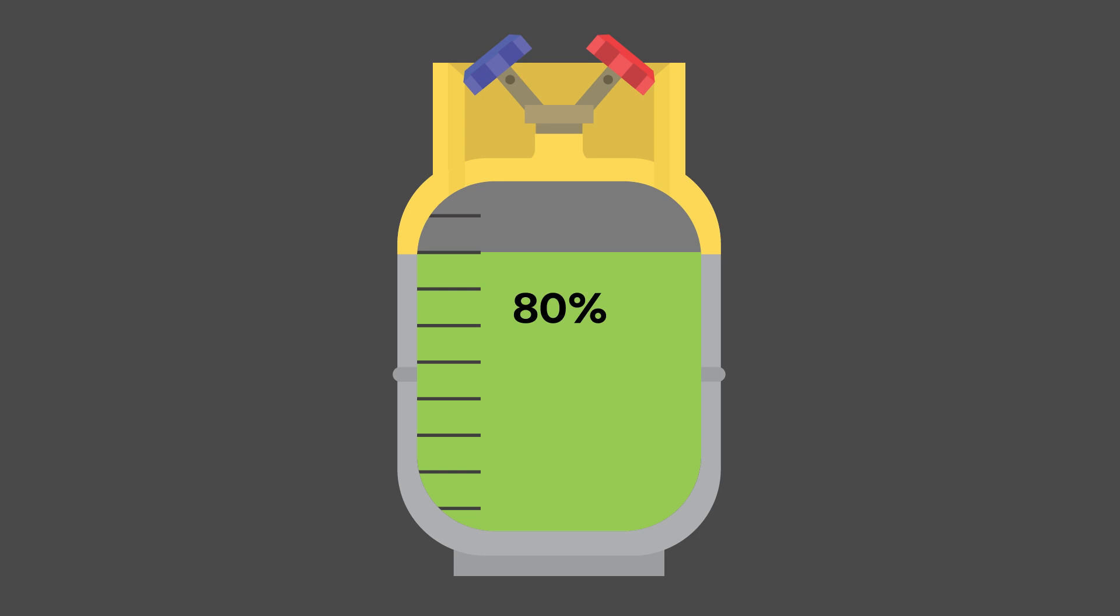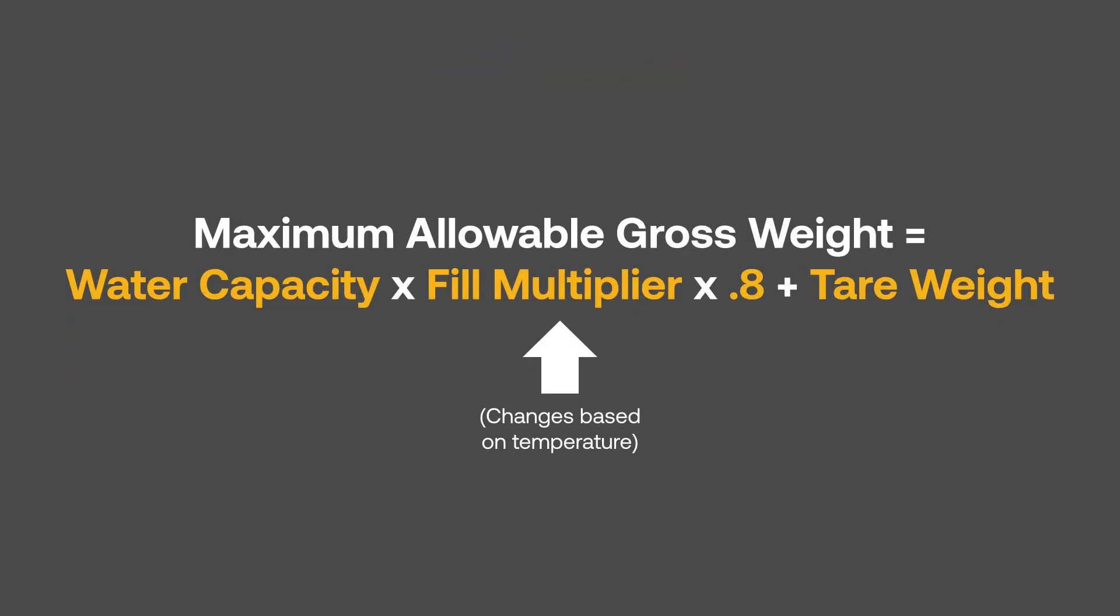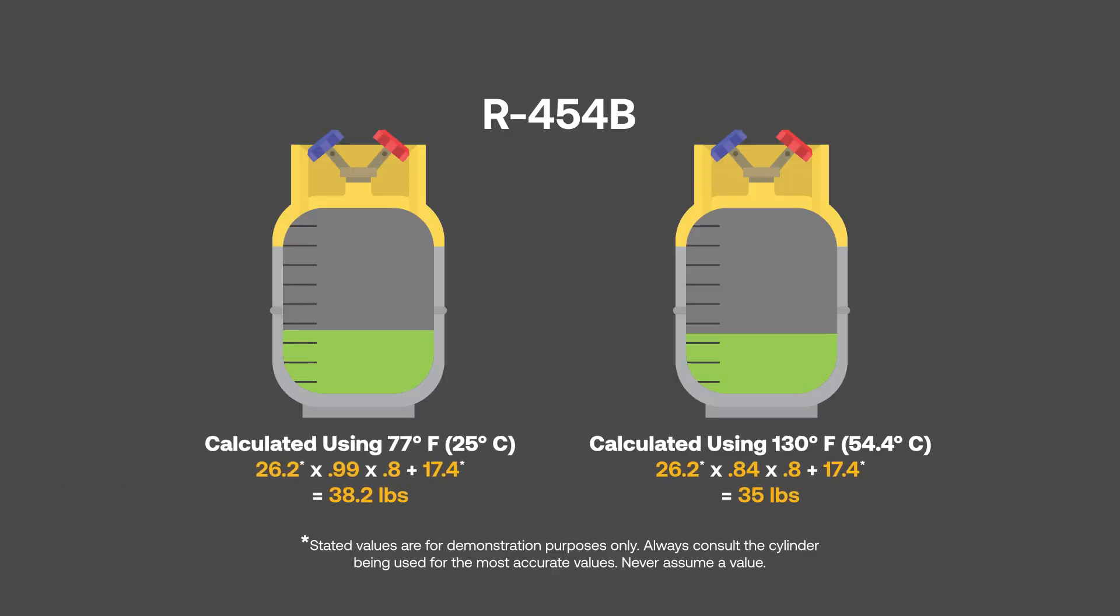In fact, the more correct way is to calculate the refrigerant weight to be added via the refrigerant's liquid density at a given temperature, typically 130 degrees Fahrenheit. For a greater margin of safety in high ambient areas, this operating temperature would be higher.